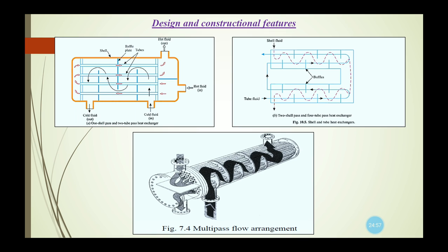So the parallel portion of the flow results in a lower effective temperature difference, but the increase in overall heat transfer coefficient will frequently compensate, so that the overall heat exchanger size will be smaller for a specific surface. Now the improvement that we achieve using this multipass heat exchanger is significantly large.